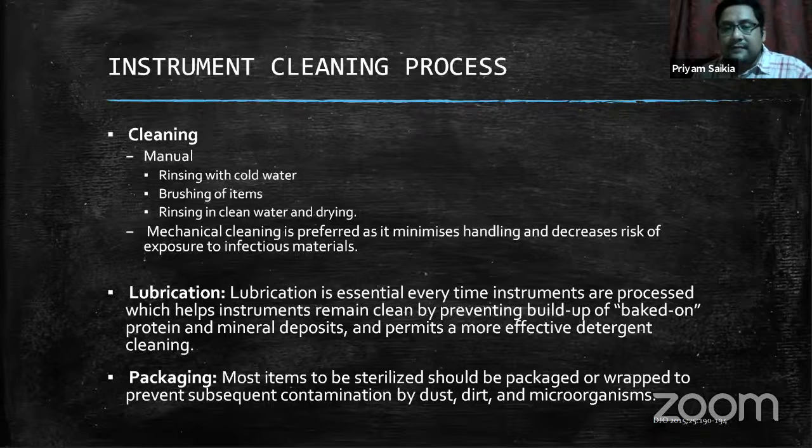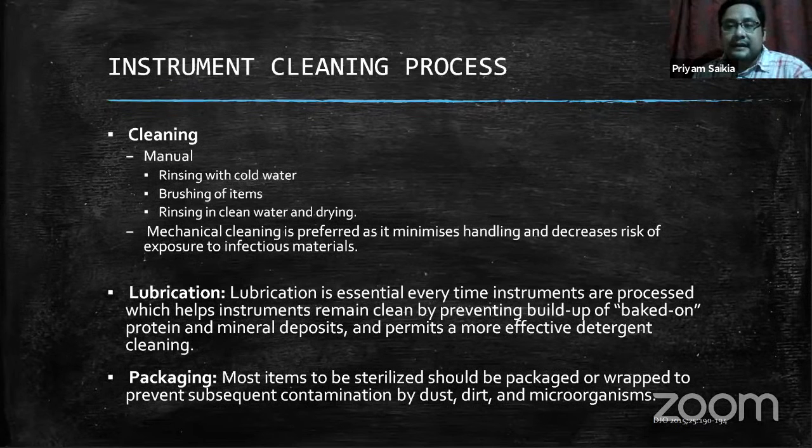And if you are using mechanical cleaning, then it is well and good. It is an automated process. Many instruments would need the use of manufacturer recommended lubricants. Otherwise, the hinges will simply stop working and there will be buildup of baked-on protein. And then subsequently, they are allowed to dry. And after drying, they should be packaged so as to send them for sterilization.